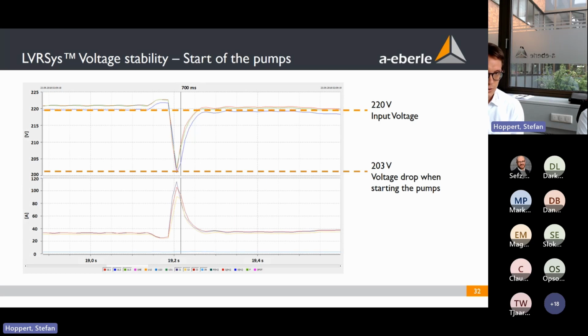Here you can see how it looks. On the upper line, the nominal voltage was here 220 volts because the voltage drop along the long line had already reduced the voltage from 230. And if they start the pumps, it goes down to 203 volts, which is too low. And the minimum voltage which the pumps were allowing was 207 volts. So every time they started and the voltage was a bit too low, they stopped working and somebody had to go there to restart them and cancel the failure.